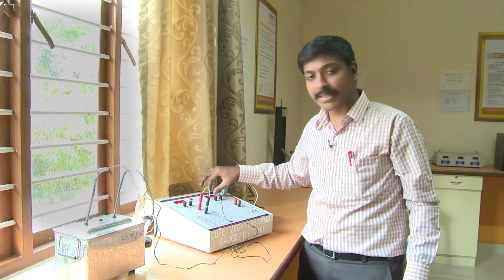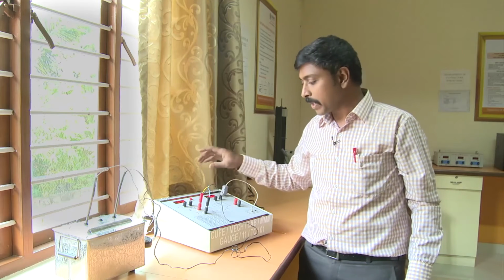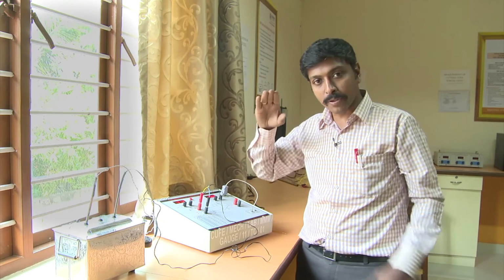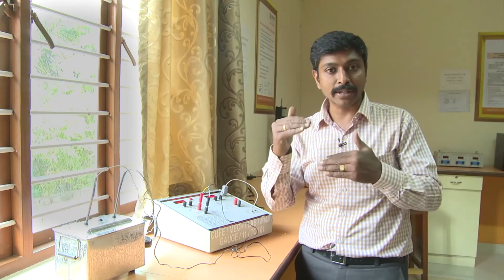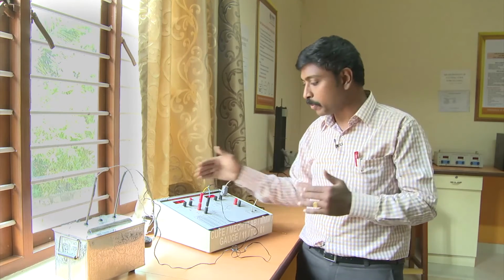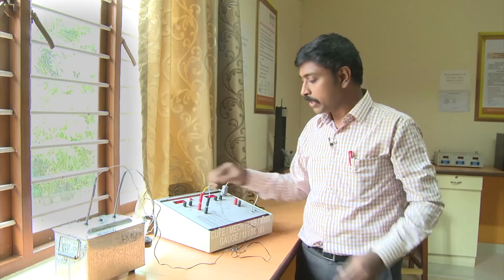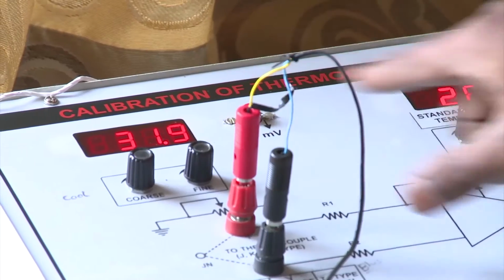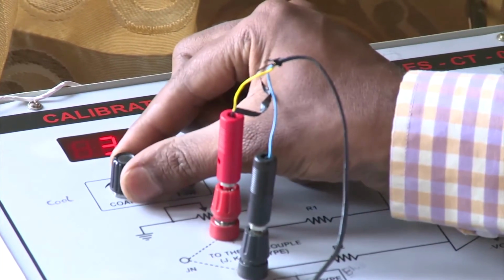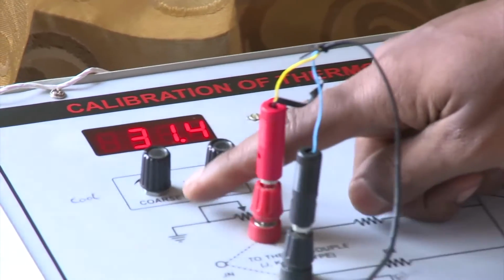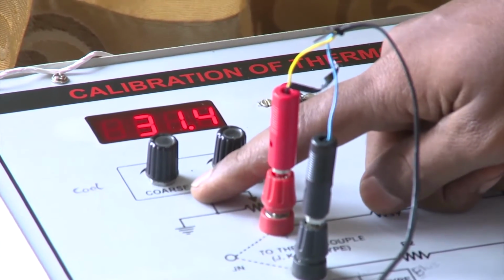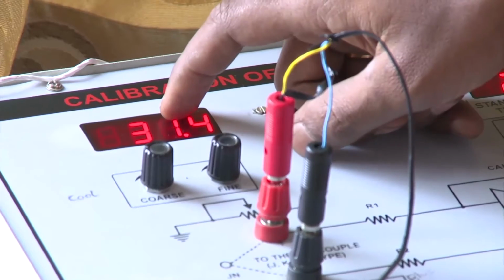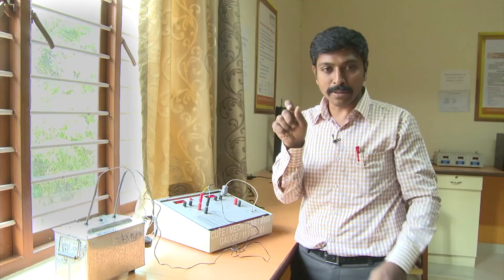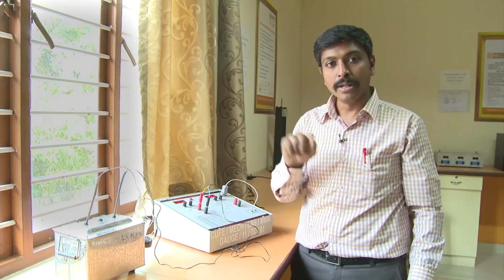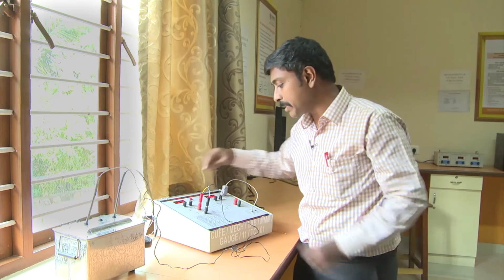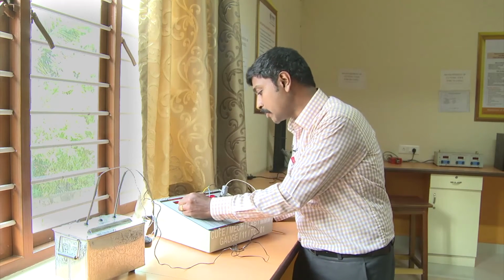So I'm going to fix this as the right value, and the other one I'm going to modify, or correct, as a zero error correction, so that both values start from the same point. So 31.9 can be reduced to 28.6 by using a coarse knob. We have a coarse and a fine knob. When you revolve the coarse knob, it provides a major change in your actual value. The fine knob is for fine tuning. You can reduce it by 0.1, 0.2 degrees centigrade. So I'm going to make a major change first, then I can go for the fine knob change.